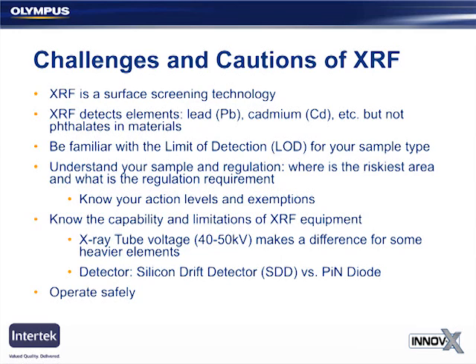The detector in the analyzer, there are a few different kinds that are common. Probably two of the most common you'll see are the silicon drift detector, SDD, or the PIN diode. The SDD is a bit newer technology. It has better sensitivity, higher performance. It can reach lower detection limits than the PIN diode can. This is especially of help if you're doing testing of a lot of metals. Usually detection limits for different elements are higher in metals than they are in lighter materials like plastic, and so the SDD will help you a bit more. The PIN diode still works for a lot of applications, but you want to make sure that the performance level that you can reach is going to match what your screening requirements are.